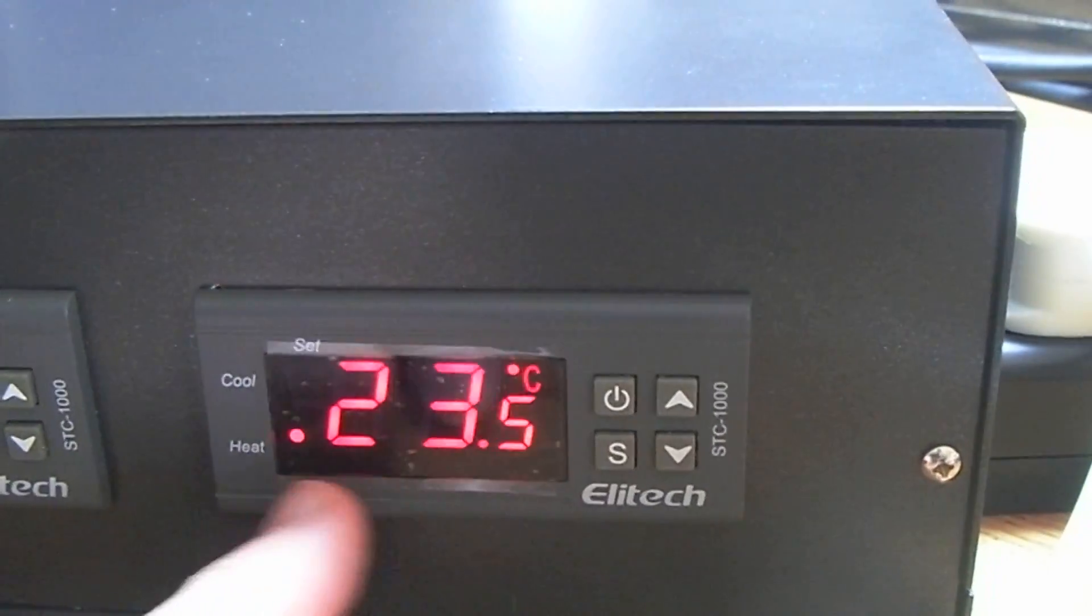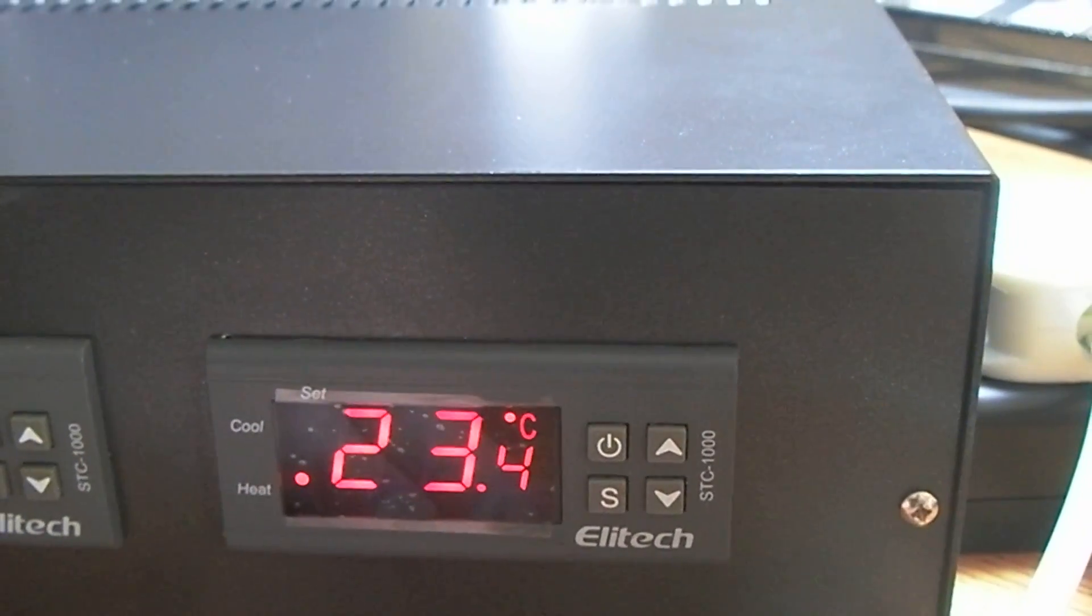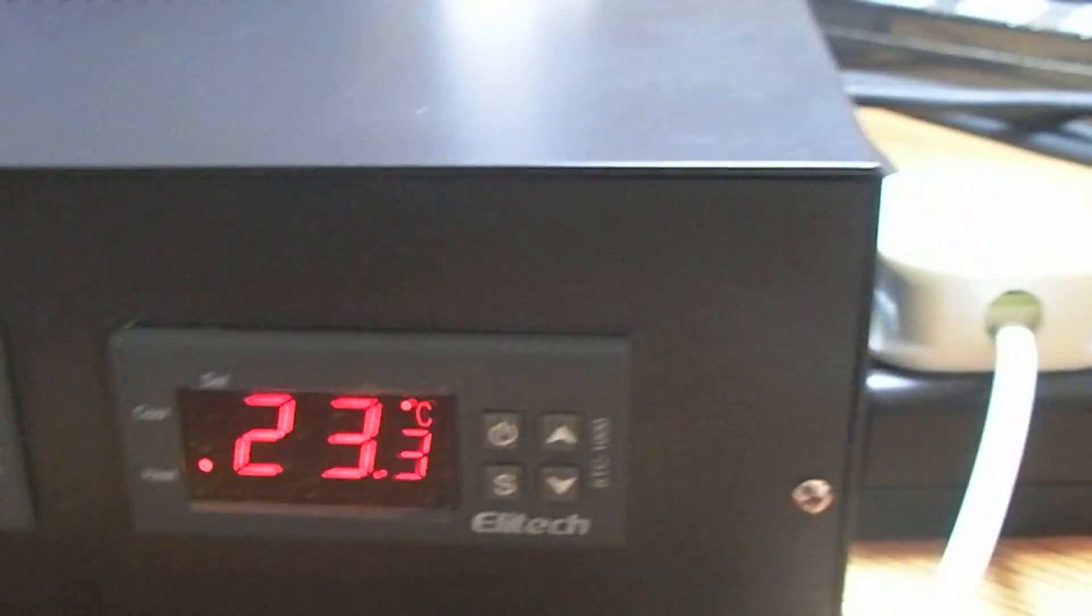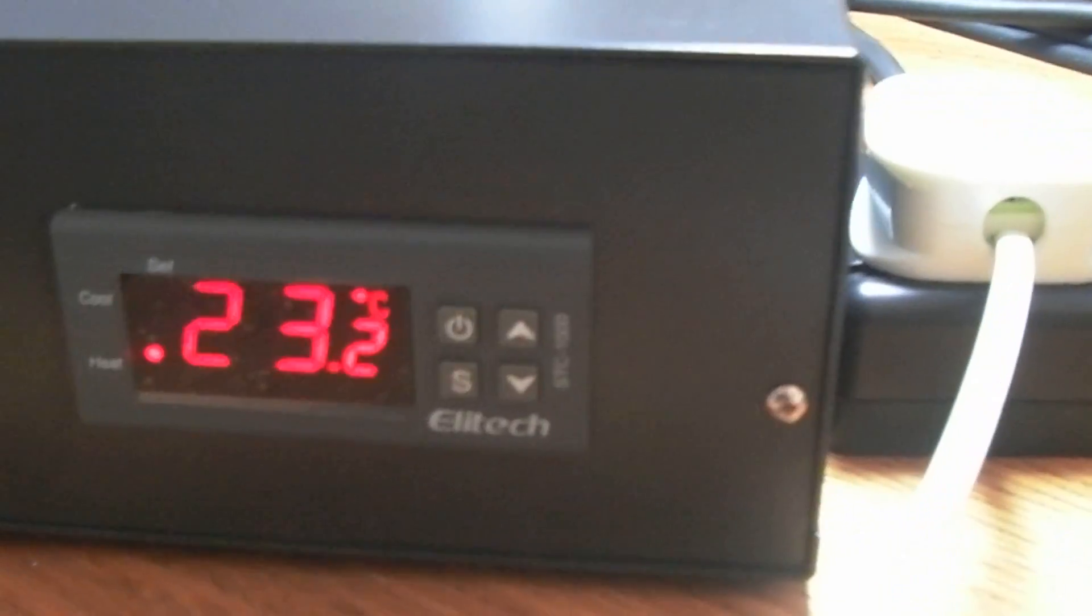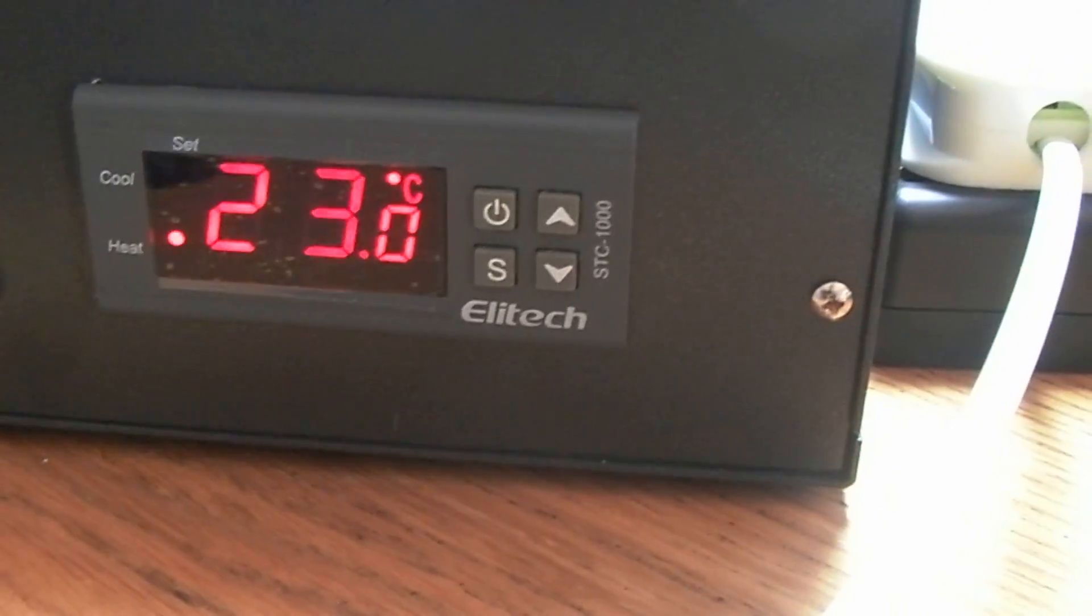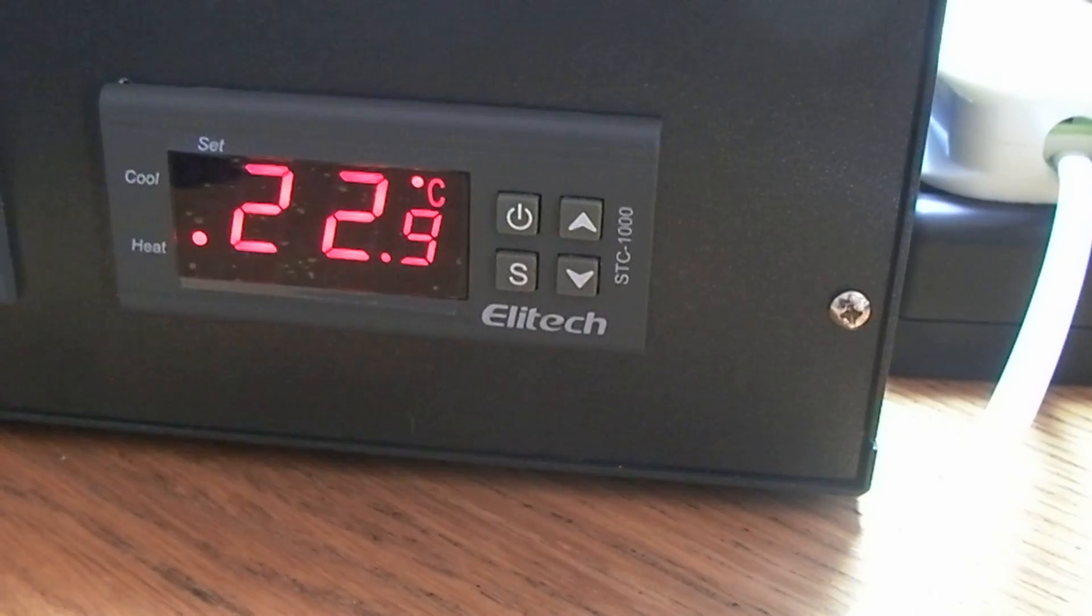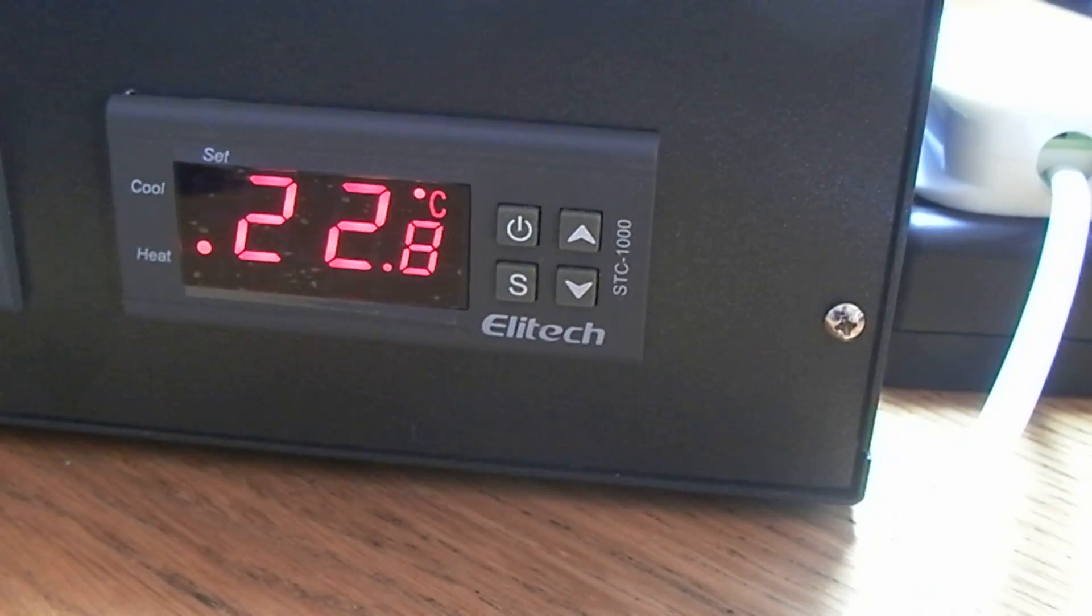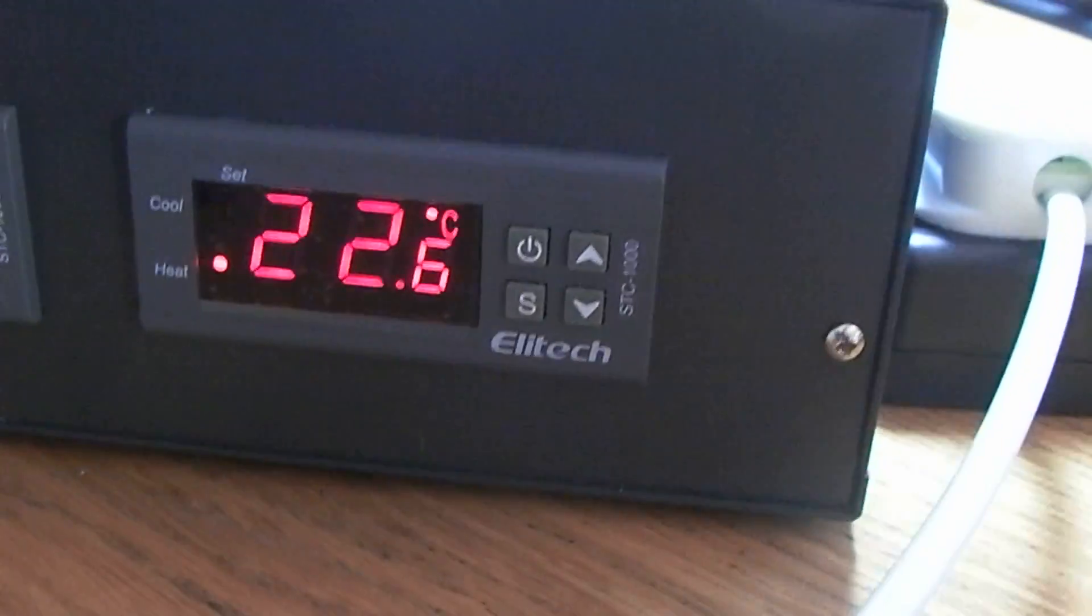Obviously you can set this to whatever you like. There's four parameters that you can adjust: the set temperature that you want to achieve, the offset, and you can set on the function 3 what they call compressor delay time. That's if you're actually using it for refrigeration purposes.